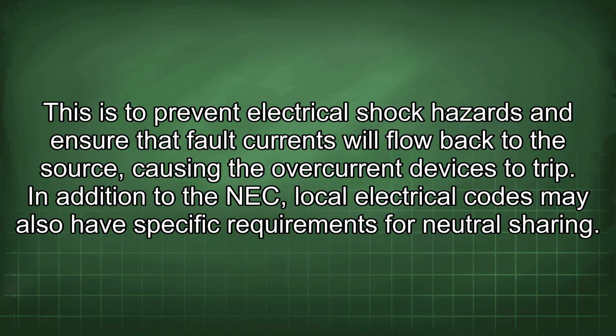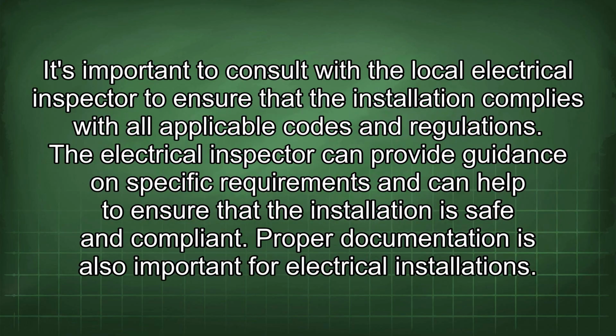This is to prevent electrical shock hazards and ensure that fault currents will flow back to the source, causing the overcurrent devices to trip. In addition to the NEC, local electrical codes may also have specific requirements for neutral sharing. It's important to consult with the local electrical inspector to ensure that the installation complies with all applicable codes and regulations.